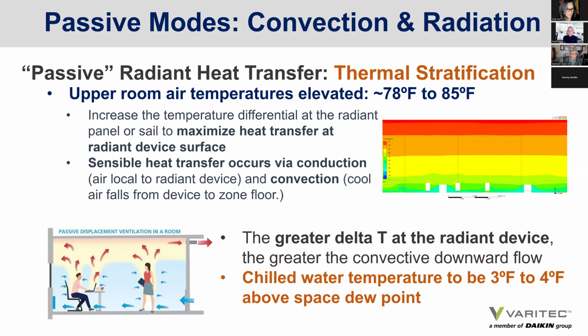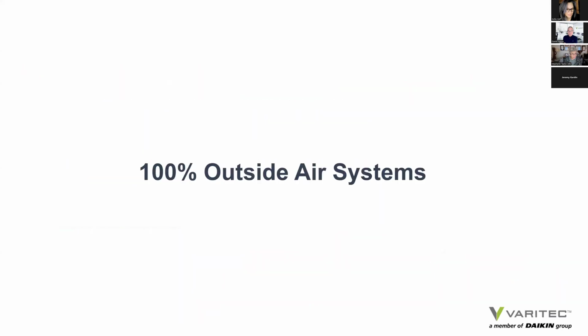To enhance that heat transfer capability with a radiant heat transfer system, you want to use a thermally stratified environment. You want to make sure that you increase the delta T at the radiant device adequately, so that in cooling mode, it can have maximum heat energy transferred to the water side of that mechanical system, because water is a more dense heat transfer medium. That sensible heat energy absorbed at the radiant device can be more efficiently removed from a building using pump energy than the otherwise added horsepower energy that would be required for mixed air handler fans. So in passive radiant systems, thermal stratification is required to optimize the performance of a radiant system.